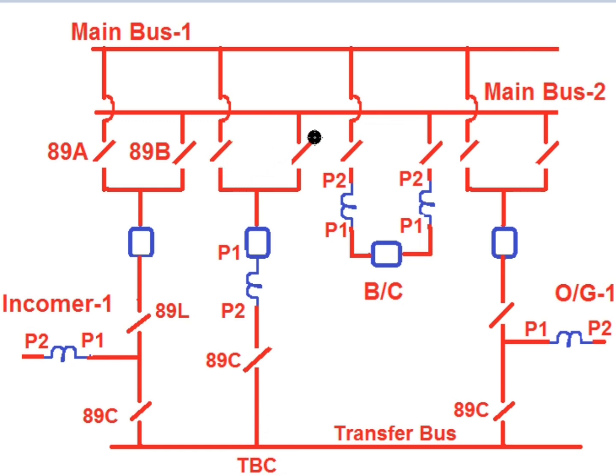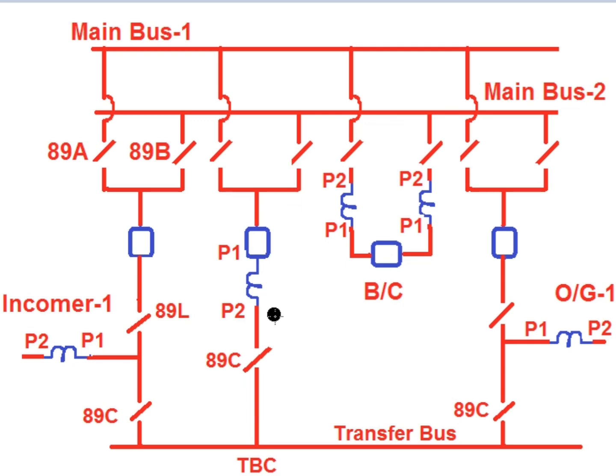The TBC bay has three isolators: 89A, 89B, and 89C. If 89A is closed, 89C is closed, and the circuit breaker is closed, then the TBC bay couples main bus 1 with the transfer bus. If 89B is closed, 89C is closed, and the circuit breaker is closed, then the TBC bay couples main bus 2 with the transfer bus.